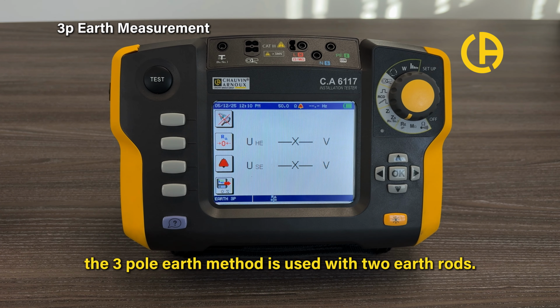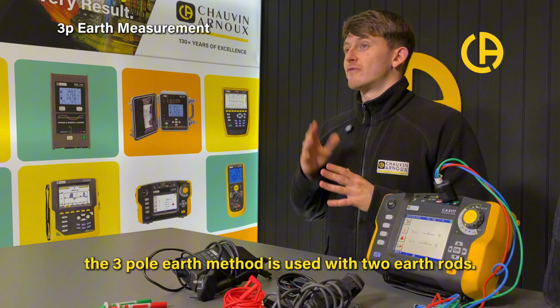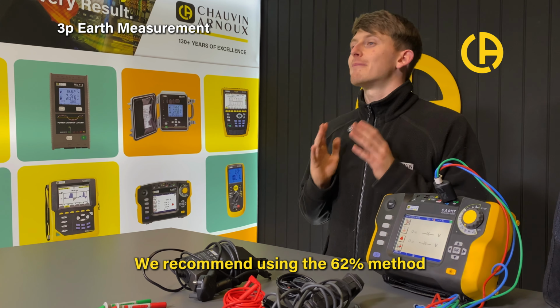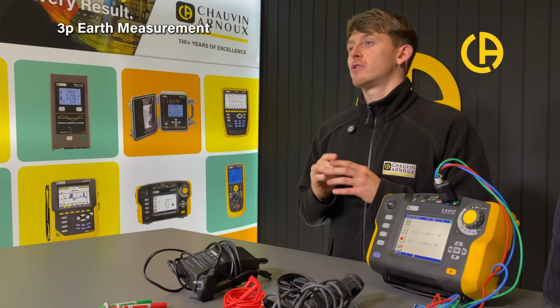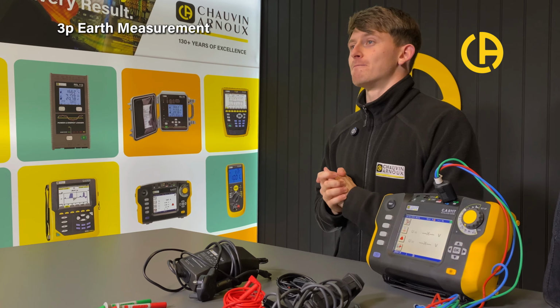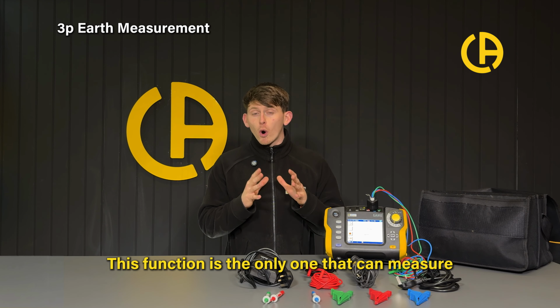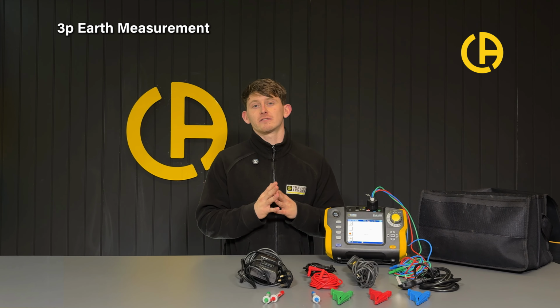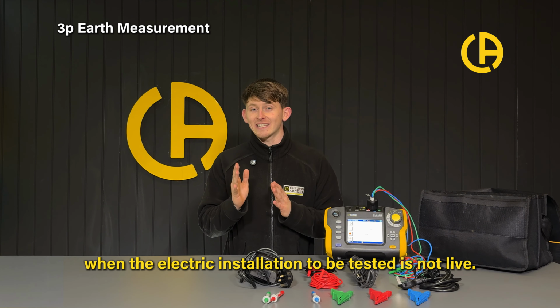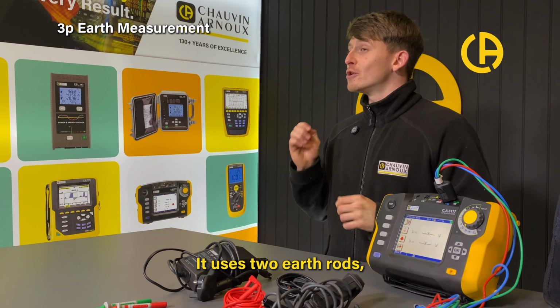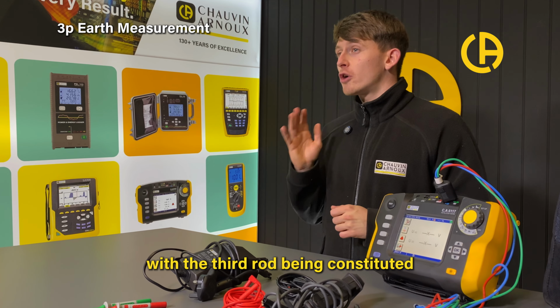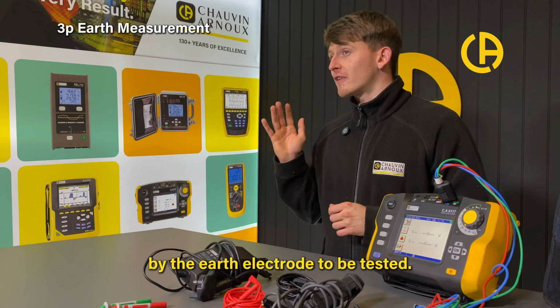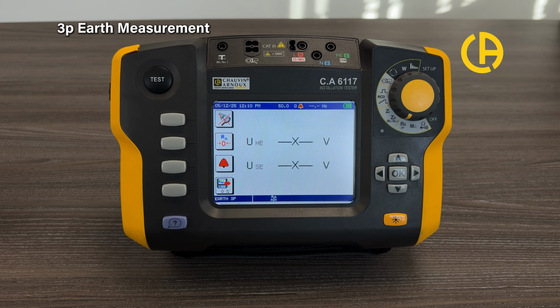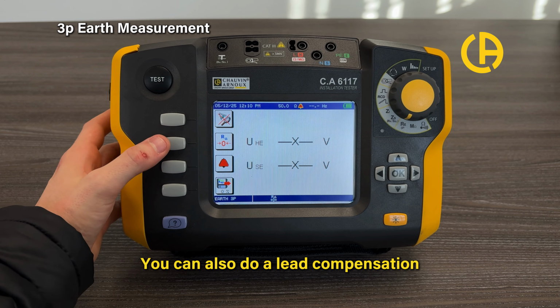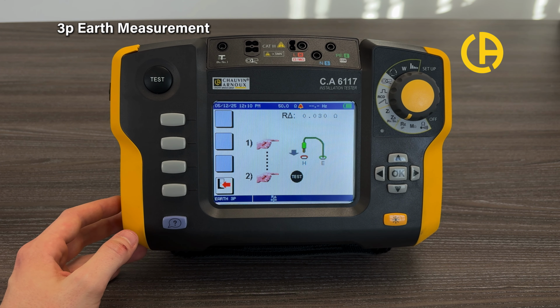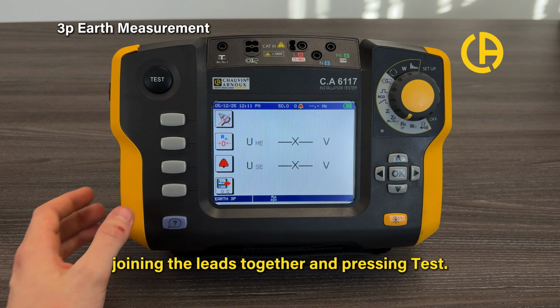So the 3-pole earth method is used with 2 earth rods. We recommend using the 62% method when using the CA6117. This function is the only one that can measure an earth resistance when the electric installation to be tested is not live. It uses 2 earth rods, with the 3rd rod being constituted by the earth electrode to be tested. You can also do a lead compensation by clicking the R button, joining the leads together and pressing test.